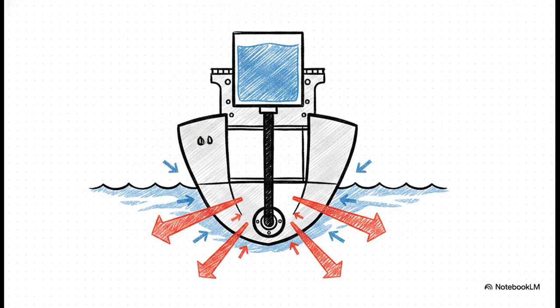And this brilliantly illustrates how everything we've learned ties together. Remember our earlier explainer on operating drafts? When a drill ship ballasts down from its transit draft to its 11-meter drilling draft, it sits much deeper in the water. At that depth, the external sea pressure pushing inward against the thruster seals easily exceeds 2 bar. Therefore, the gravity tank has to be elevated high enough inside the hull to guarantee the outward-pushing oil pressure comfortably beats that 2+ bar at all times, no matter how deep the ship drafts.